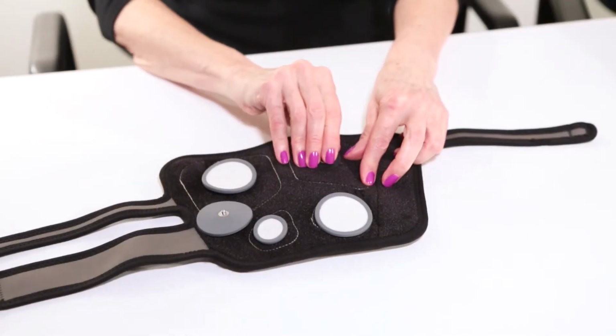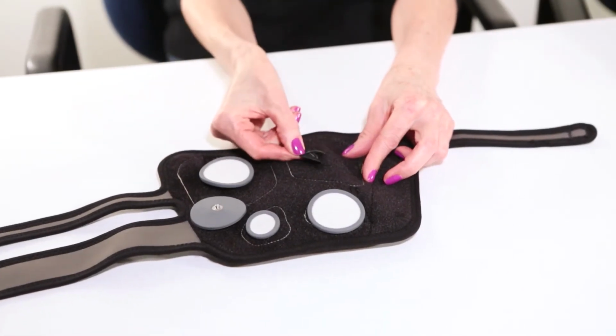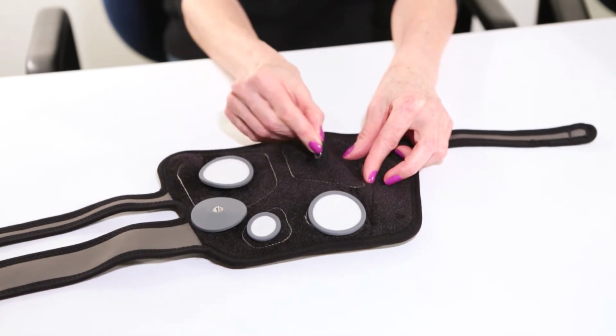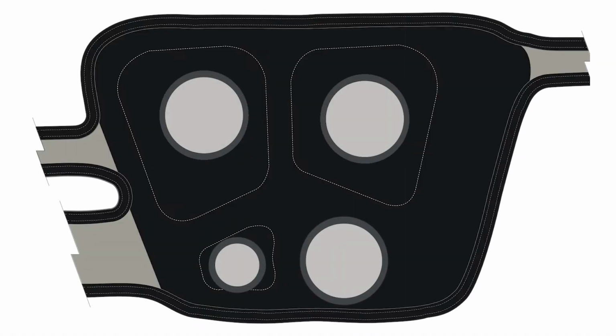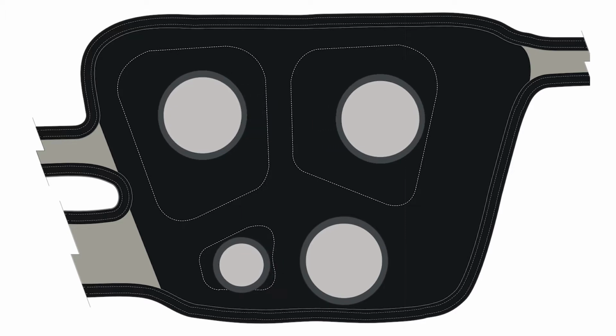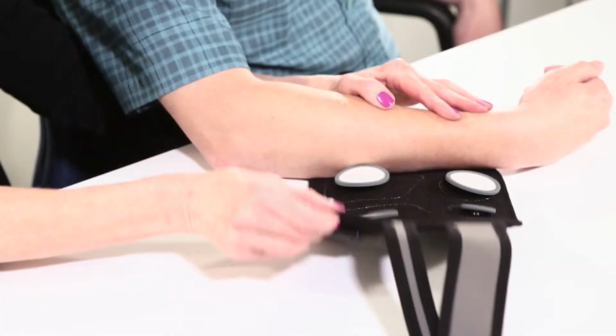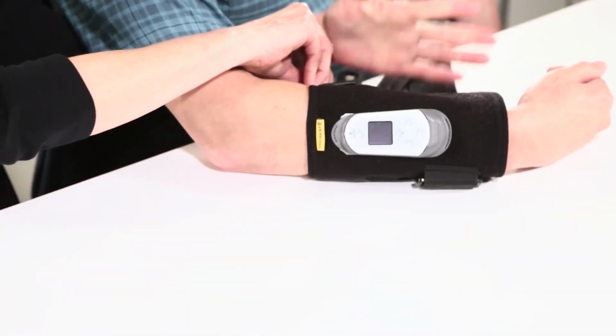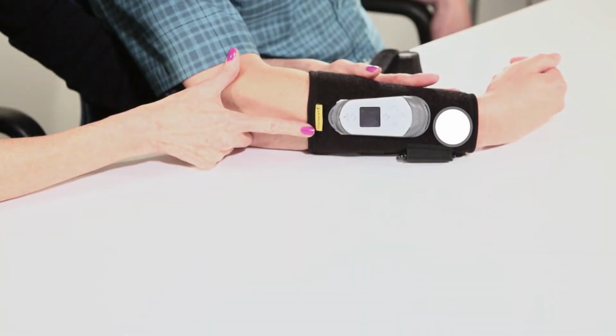When positioning the electrode, take care not to bend or overstretch the connecting wires. In general, for smaller forearms, the electrodes will need to be closer to the middle, and for larger forearms, they'll need to be towards the outside. Lay the garment flat over the forearm so that the reference electrode sits at the base of the wrist where a watch would be. The hand opening electrode should be right around the middle of the forearm.